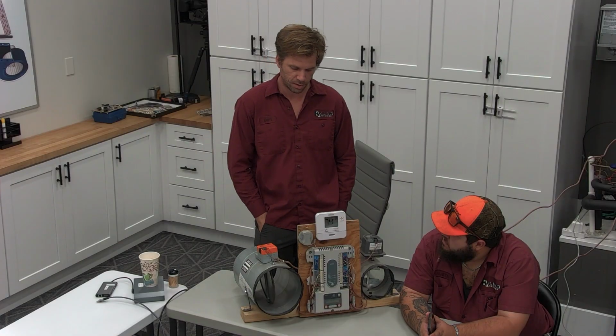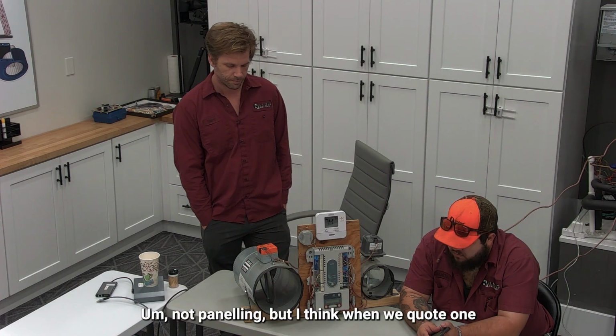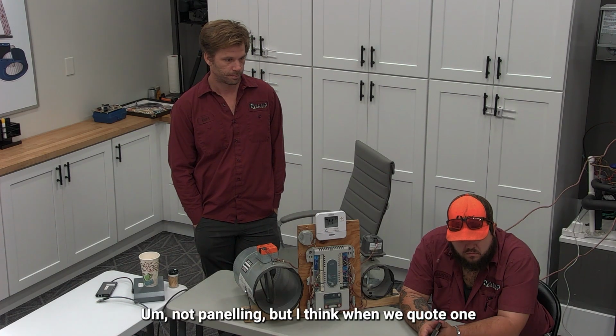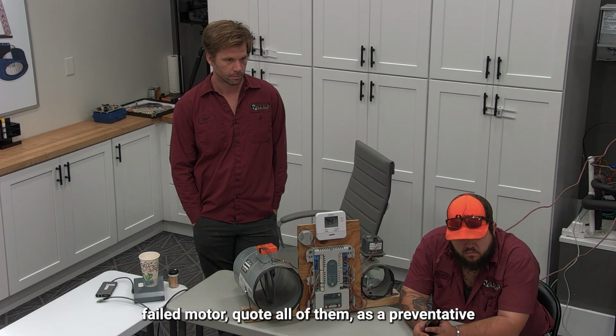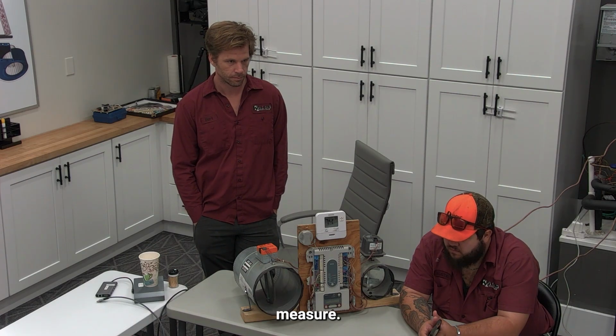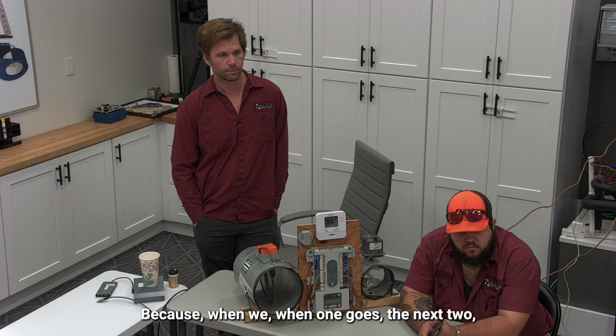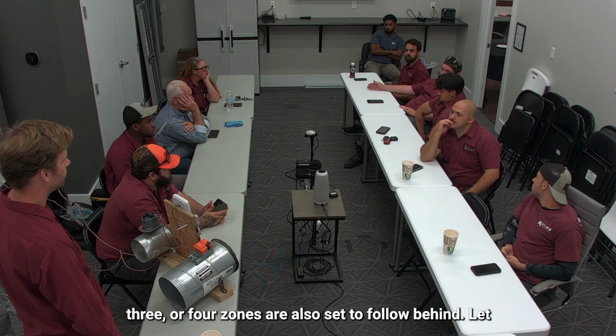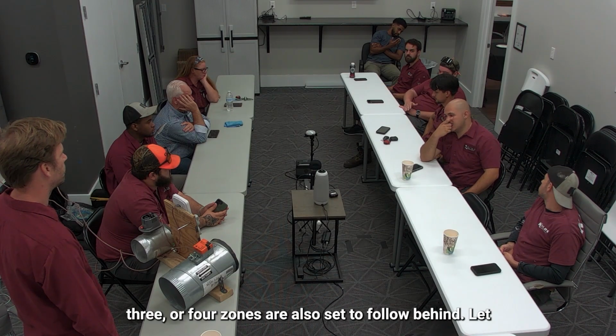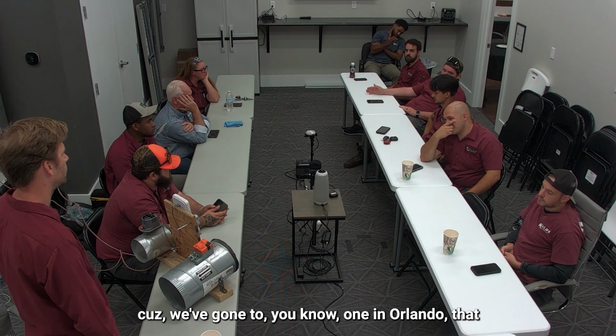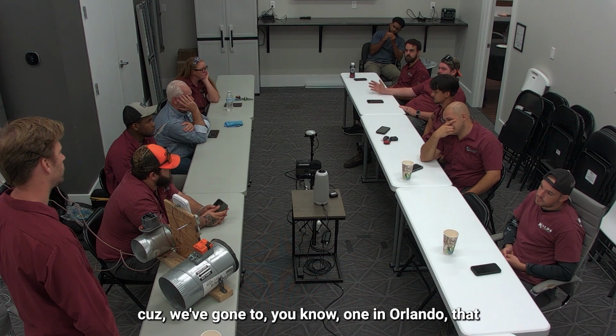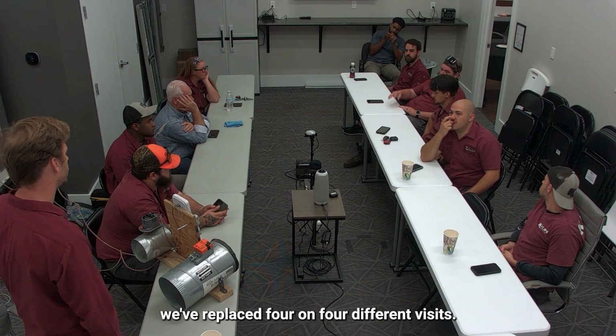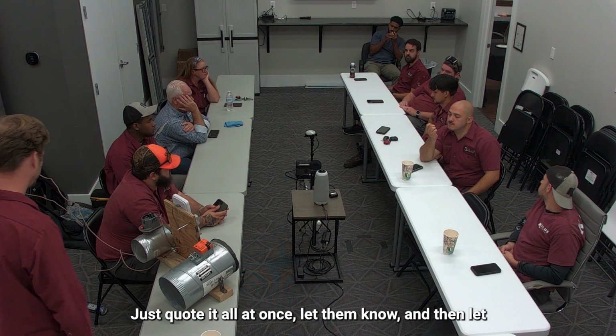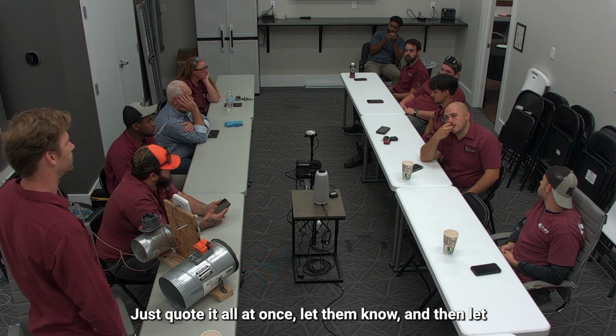So that's great. Any questions on damper systems, issues that you've run into that we can talk about? Not panel, but I think when we quote one failed motor, quote all of them as a preventative measure. Because when one goes, the next 2, 3, or 4 zones are also set to follow behind. Let the homeowner know as a preventative measure, because we've gone to one in Orlando that we've replaced 4 on 4 different visits.